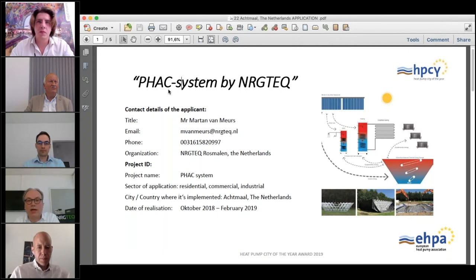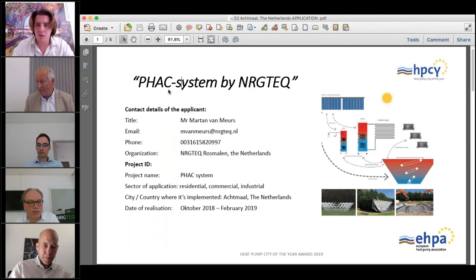Then we use our high temperature heat pump. It can cope with these various source temperatures. It can go as low as, of course, 5 degrees, but it can go as high as up to 30 or 40 degrees Celsius. We can run the heat pump with these source temperatures and provide an output temperature of up to 80 degrees Celsius. This output is stored in the thermal storage. This is on the right lower corner.